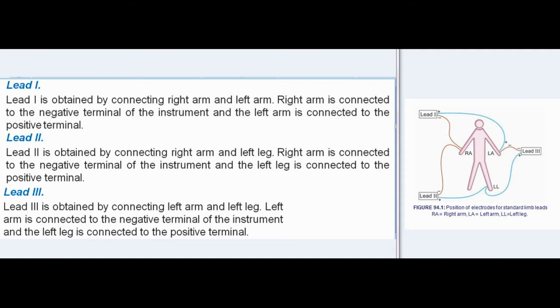Lead II is obtained by connecting the right arm and left leg; right arm is connected to the negative terminal and left leg to the positive terminal. Lead III is obtained by connecting left arm and left leg; left arm is connected to the negative terminal and the left leg to the positive terminal.